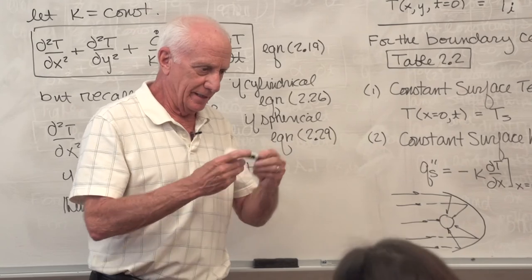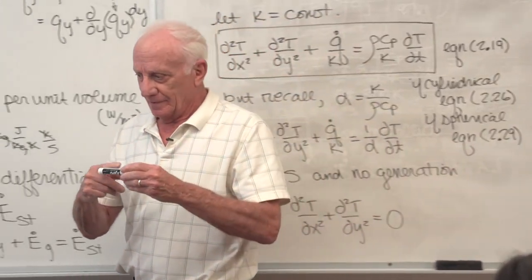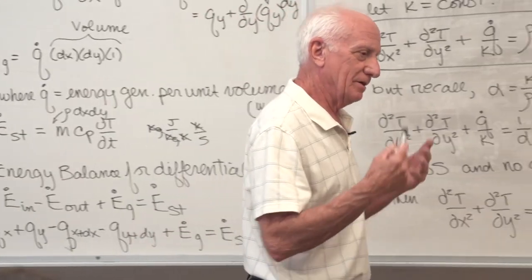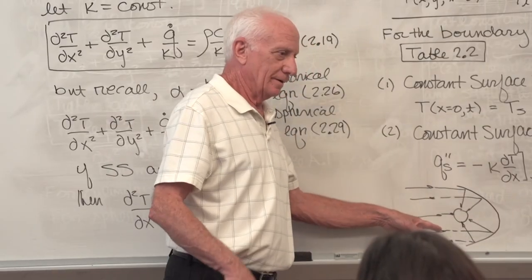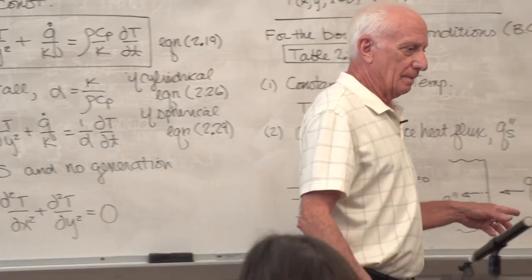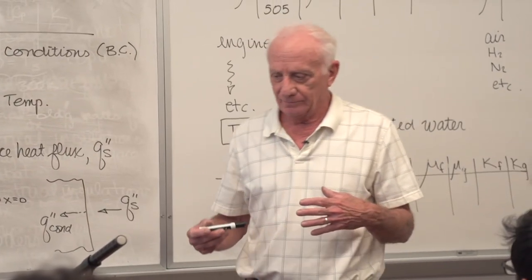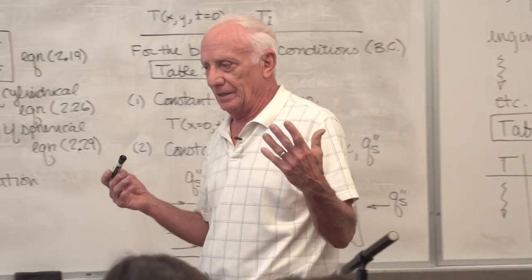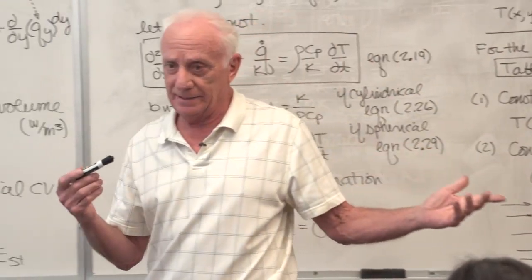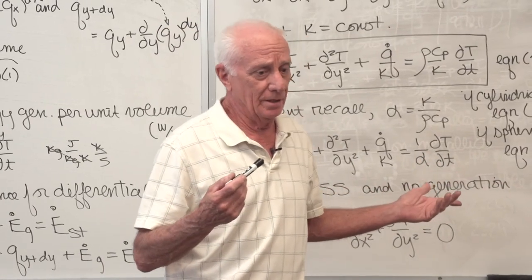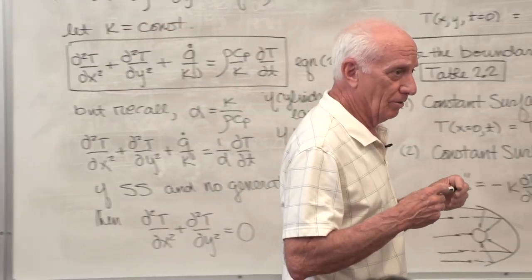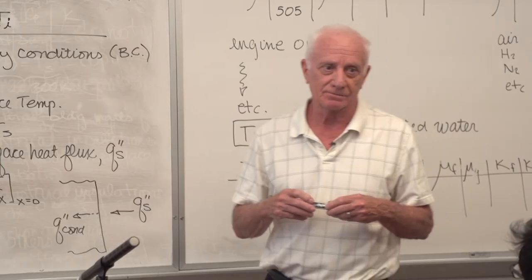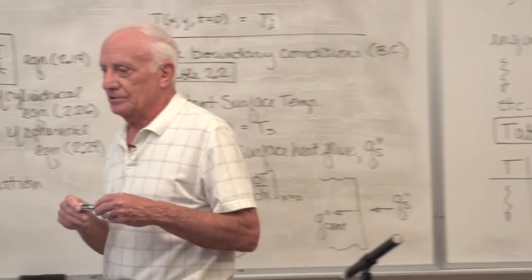Sometimes they wrap heaters around a pipe if they're worried about the temperature of the fluid in there. I'll give you an example. The solar collector field here carries oil out to the collectors, and then at night, they turn the collectors off, before sunset obviously. So the oil is sitting out there all night long, and in Southern California, typically they're in the high desert, and the nights up there, oh, it can get freezing. Oil gets really cold. What you don't want to do is turn those pumps on in the morning with cold oil. Ooh, the viscosity is really big. Not good.